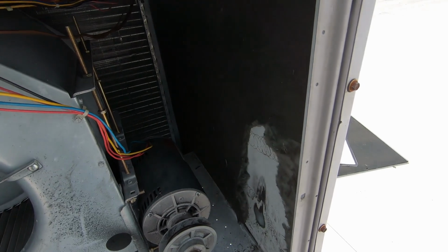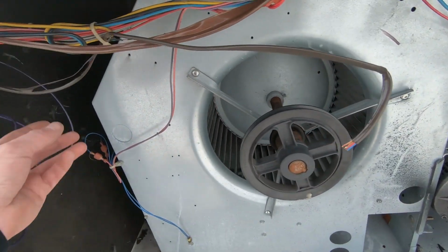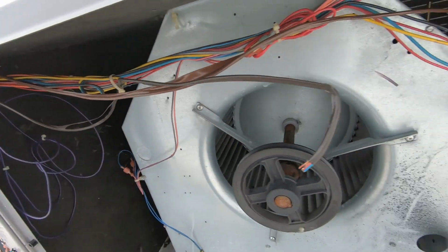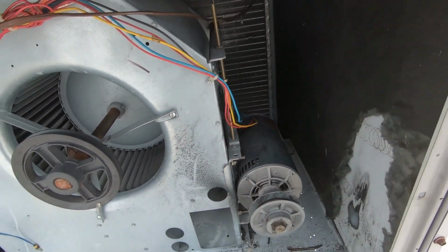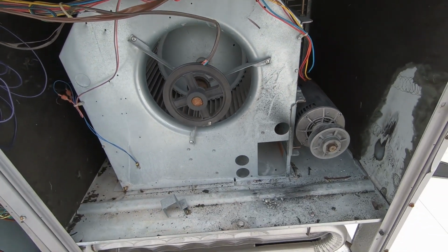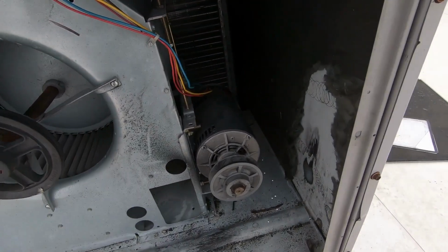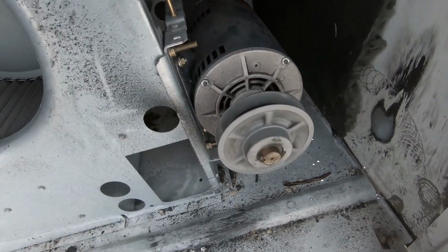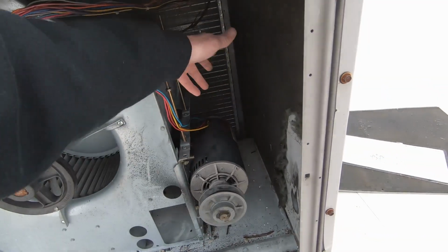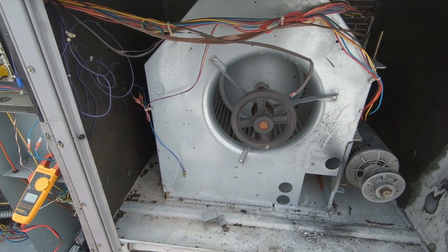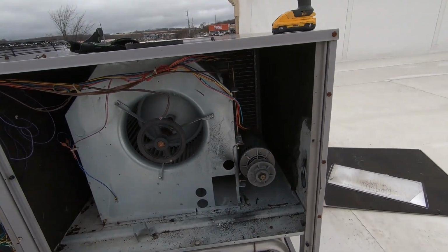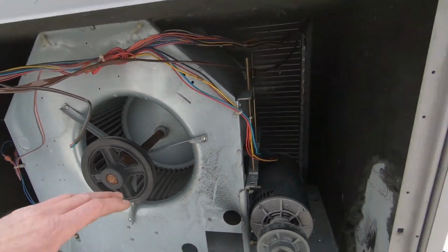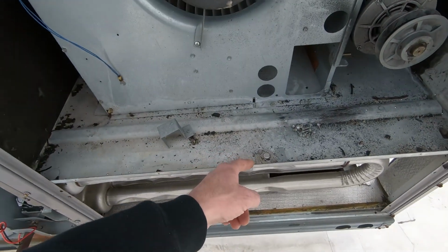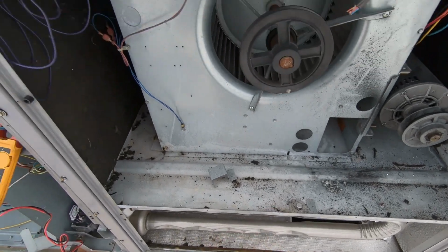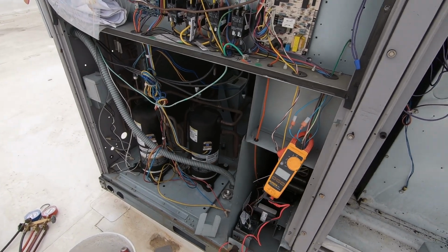With what it's already gone through, the heat, clearly the heat was enough to melt these wires. I don't even want to know what it did to the inside of this. I know that it's testing good, but literally, if we had smell-o-vision, I know what a bad blower motor smells like, and it's quite loud. Plus, I want to see what the wiring looks like. So they're getting a blower motor, they're getting new filters, they're getting an in-depth evaluation of this wiring. They're certainly getting a new limit switch wired in and fully operational. I'm going to throw the rollout in too.